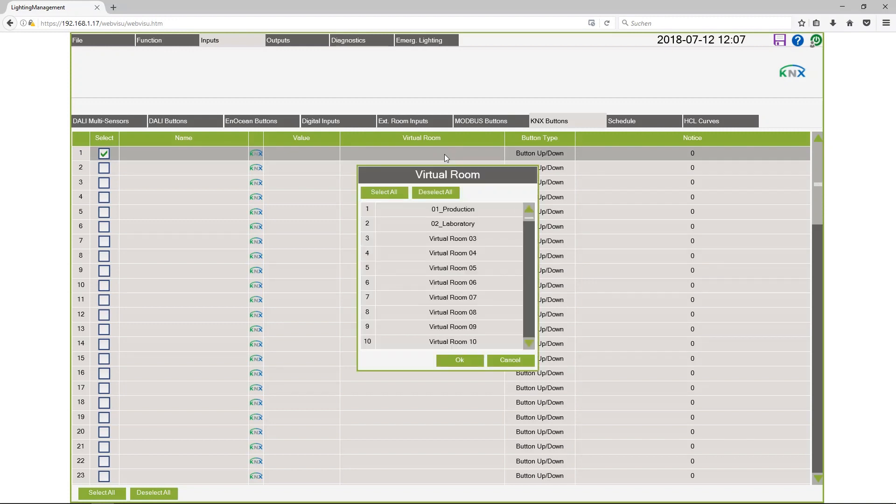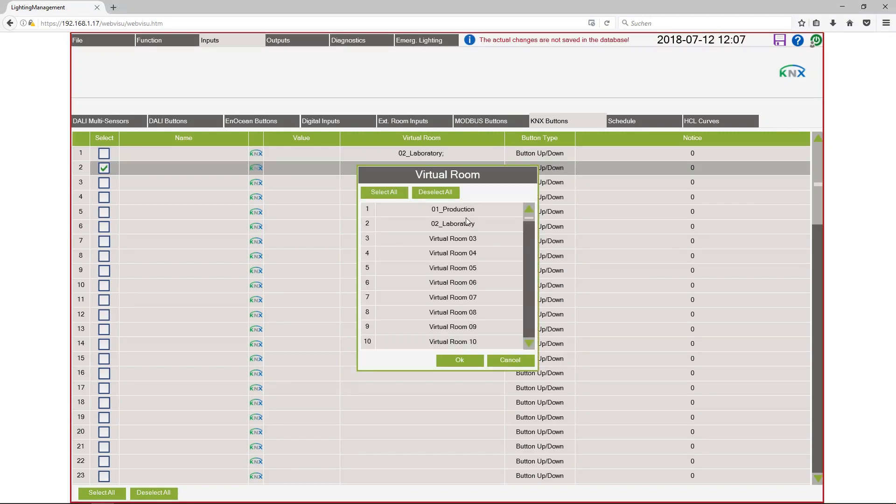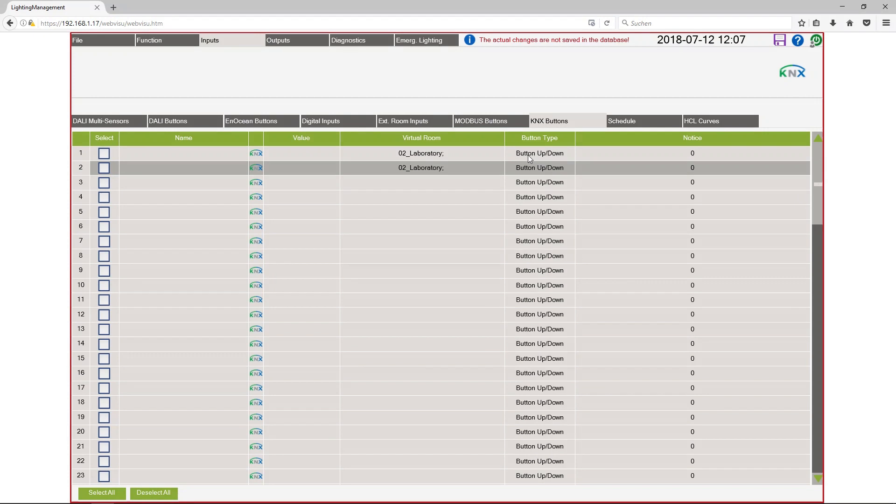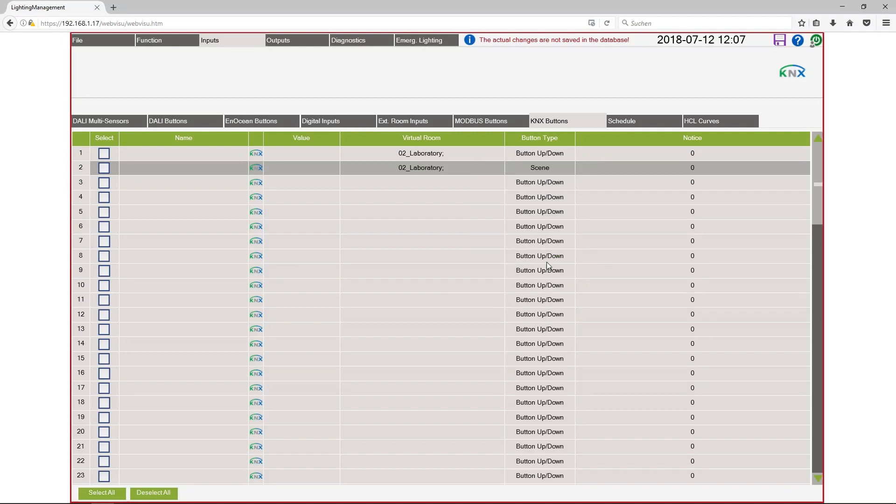So I select the right virtual room laboratory, for the second one the same. Laboratory. The button type for the first channel button up down is correct so can be used for dimming. But the second one I want to use to call a scene. So I change the button type to scene.